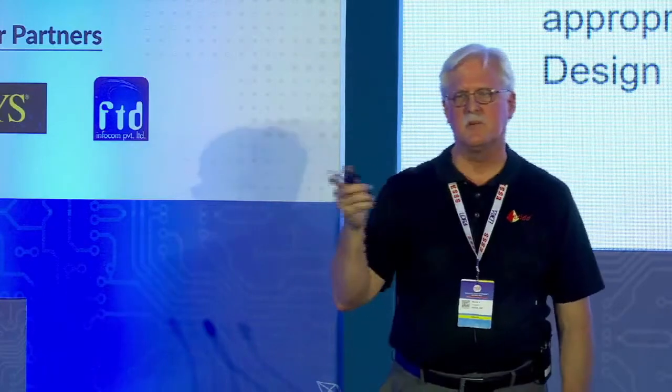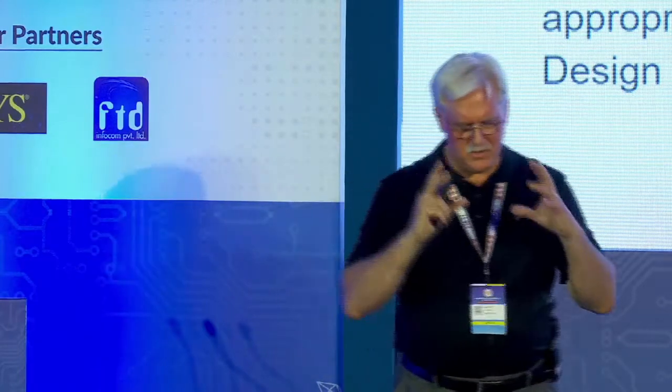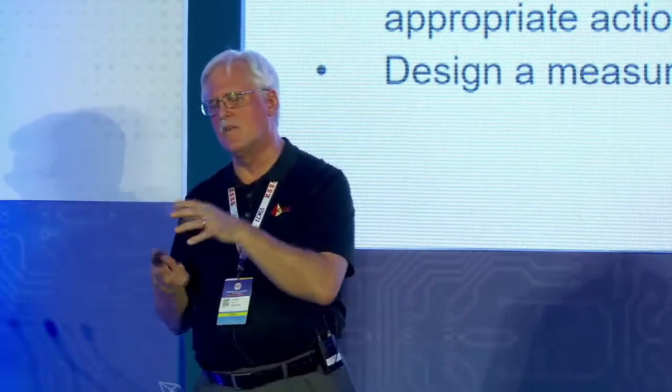And the way that you do that is you look at each individual component and you isolate and study that component as you have it designed and ask, well, what happens if things go wrong with that? So by identifying things that can go wrong, they're actually referred to as deviations in that product, you can build into your system mitigation for those deviations and help improve the strength or the robustness of your product.